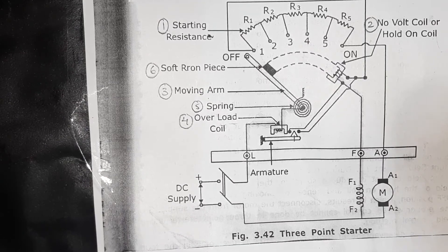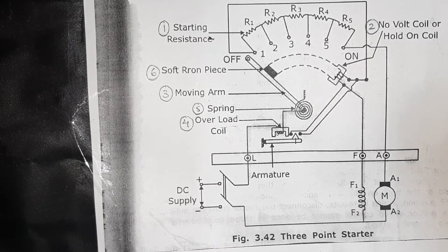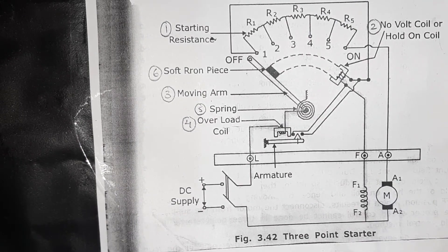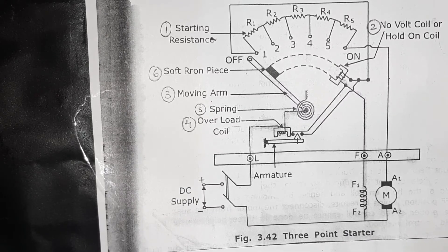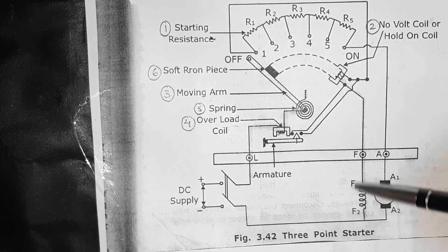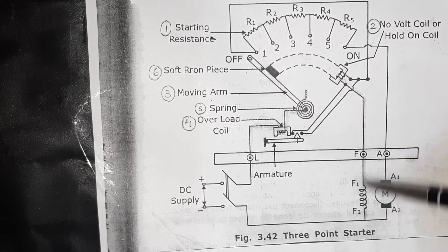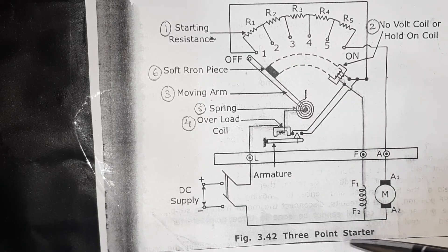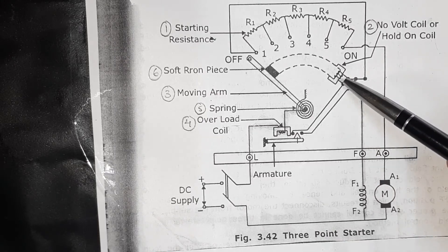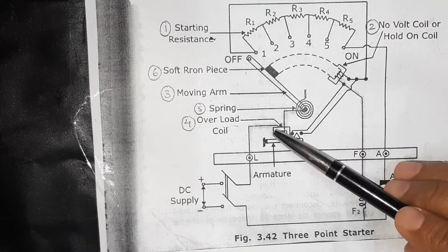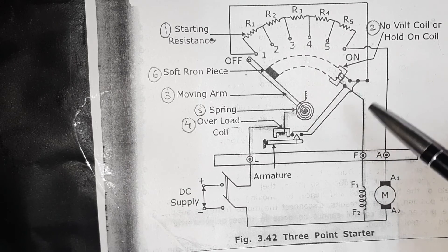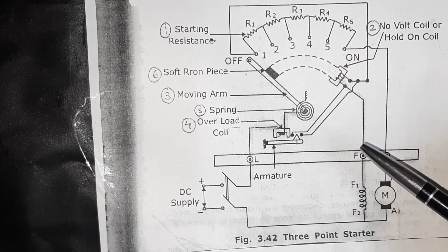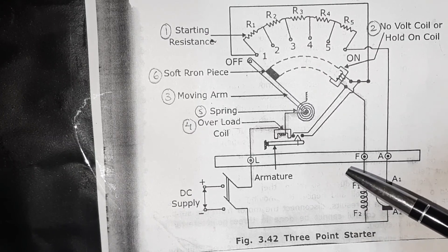In the three-point starter, there is one disadvantage. Suppose we have to speed-control the DC motor using the field control method. In the field control method, we reduce the field current. If this field current is reduced too much, since it passes through the hold-on coil, the hold-on coil will demagnetize even though there is no fault in the DC motor. Hence the moving arm is pulled back to the off position, resulting in disconnection of the motor from the supply. So we cannot achieve proper speed control of the motor using a three-point starter. This disadvantage will be overcome in the four-point starter. Thank you, friends.